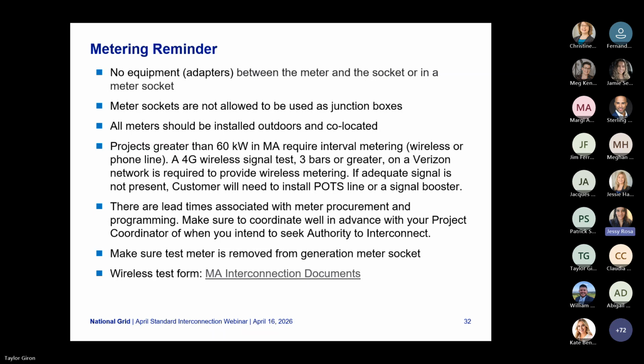Important items: in Massachusetts, it's required to install an interval meter for projects greater than 60 kW. These meters have to be wireless or on a phone line. If wireless, it's required to run a 4G wireless signal test on a Verizon network - there's a link at the bottom of the slide where you'll find the test form. If the meter is on a phone line, it must be dedicated and terminated at the meter location, and the line must be 100% copper with no exceptions. If you use fiber lines, it could fail to communicate properly, so keep that in mind.